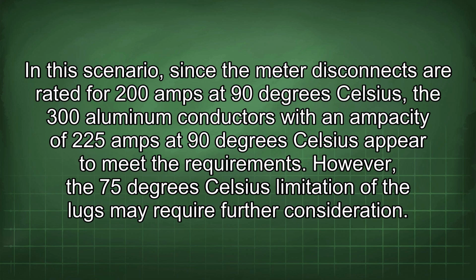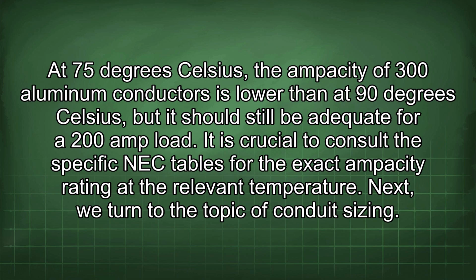In this scenario, since the meter disconnects are rated for 200 amps at 90 degrees Celsius, the 300 aluminum conductors with an ampacity of 225 amps at 90 degrees Celsius appear to meet the requirements. However, the 75 degrees Celsius limitation of the lugs may require further consideration. At 75 degrees Celsius, the ampacity of 300 aluminum conductors is lower than at 90 degrees Celsius, but it should still be adequate for a 200 amp load. It is crucial to consult the specific NEC tables for the exact ampacity rating at the relevant temperature.